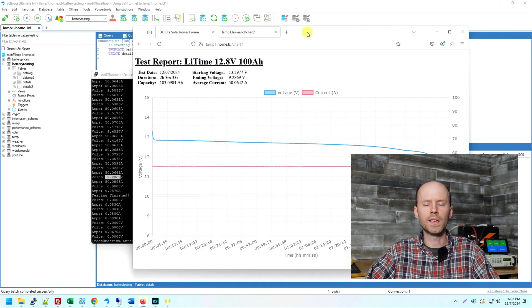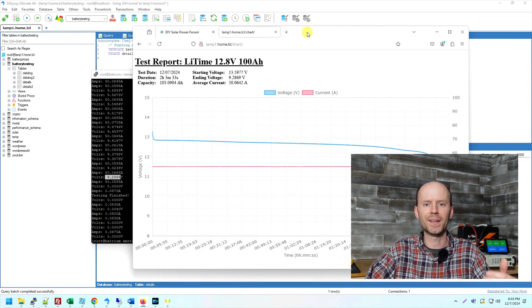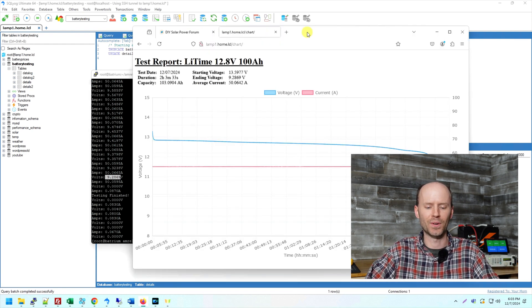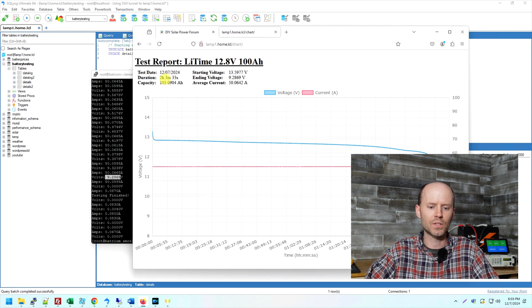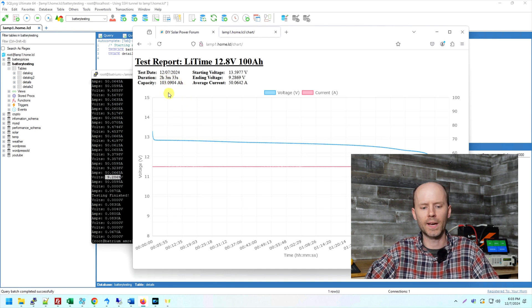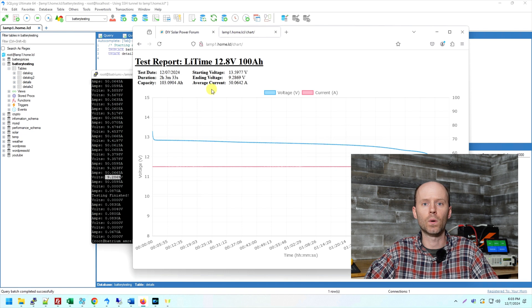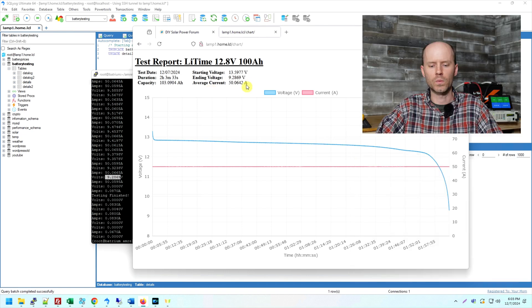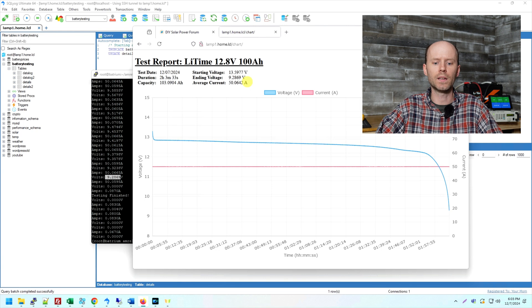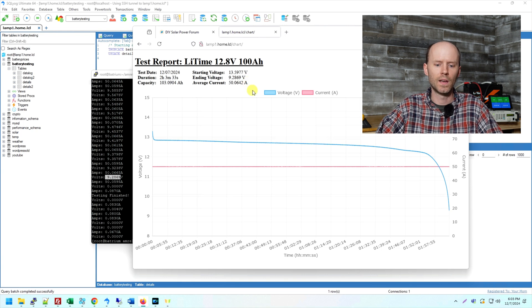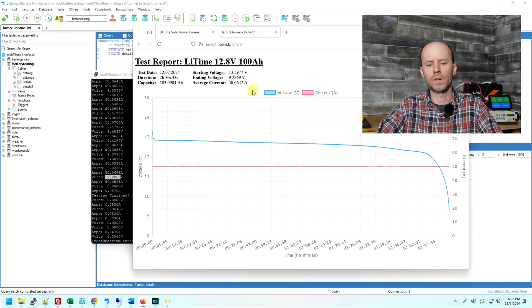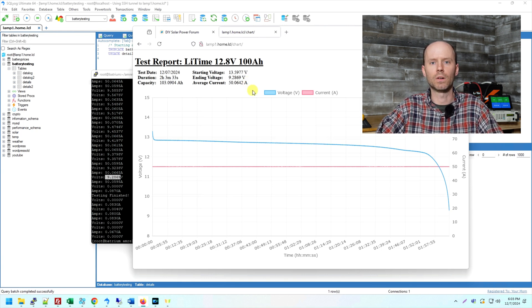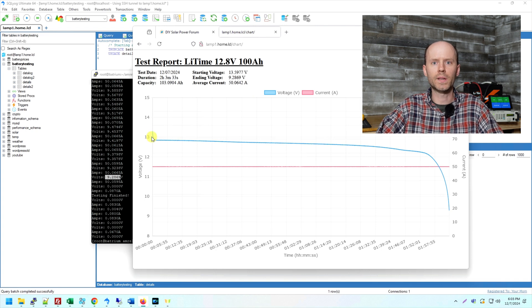And we can see the completed graph and the completed test report for this battery. So the test took two hours, three minutes and 33 seconds. The capacity was 103.0904 amp hours. We started at 13.59 volts and we ended at 9.28 volts. And the average discharge current throughout the test was 50.06 amps. And here we can see our voltage discharge profile. Very, very cool. This is very exciting.